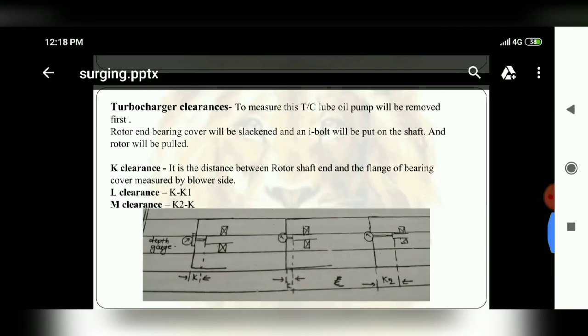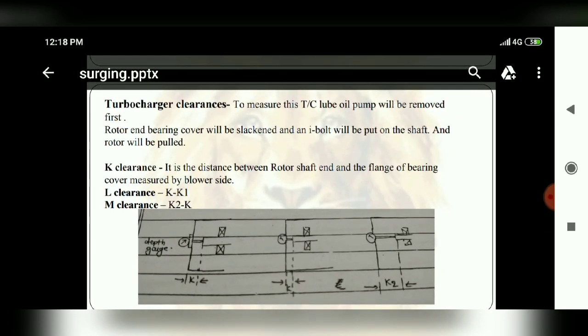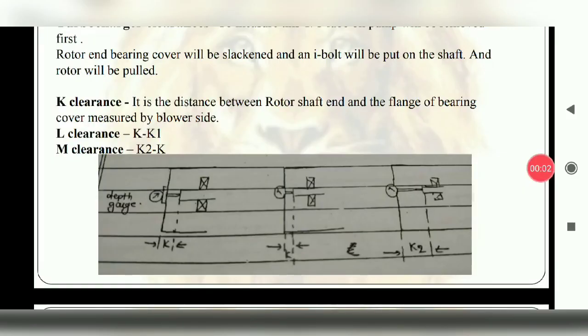So what are you going to do? We will remove the lube oil pump and then the end of the rotor we will fix the eye bolt. We will fix the eye bolt on the shaft. So the gap of bearing cover and the rotor shaft will be reduced, we have called K1. So L will be K minus K1.